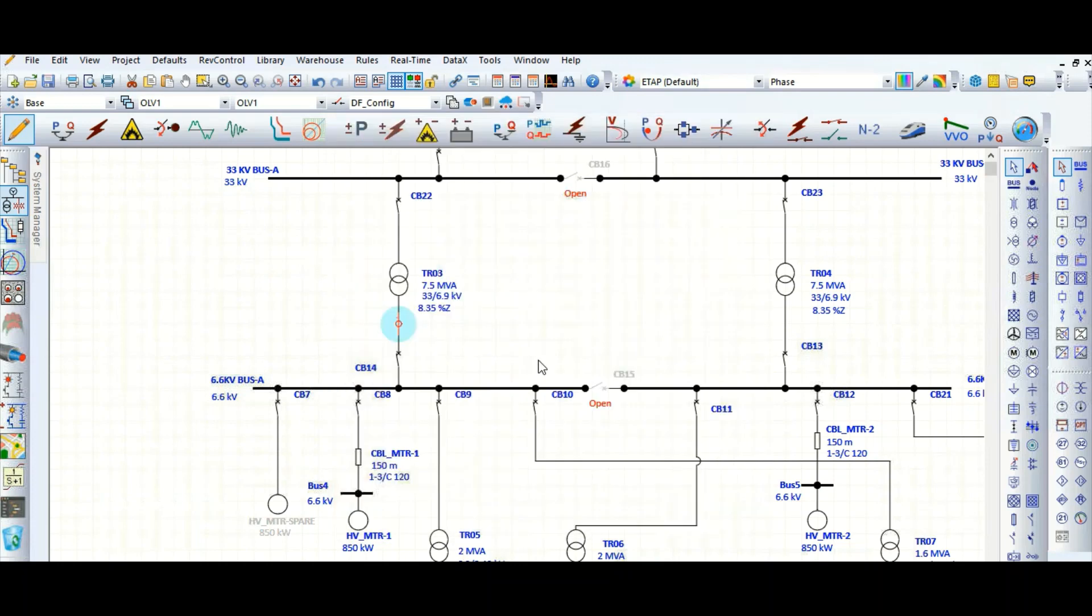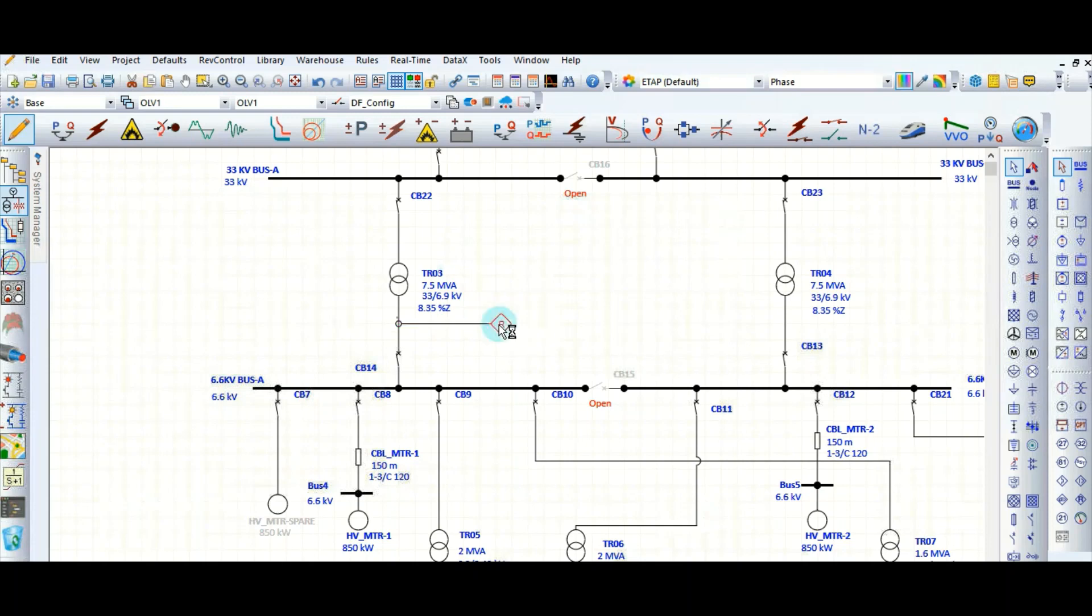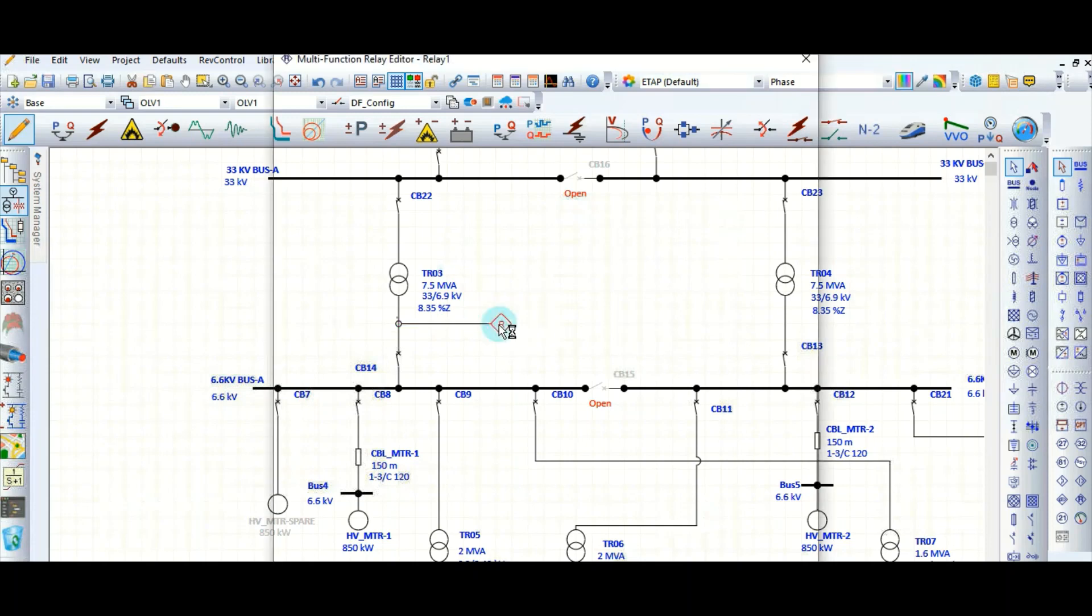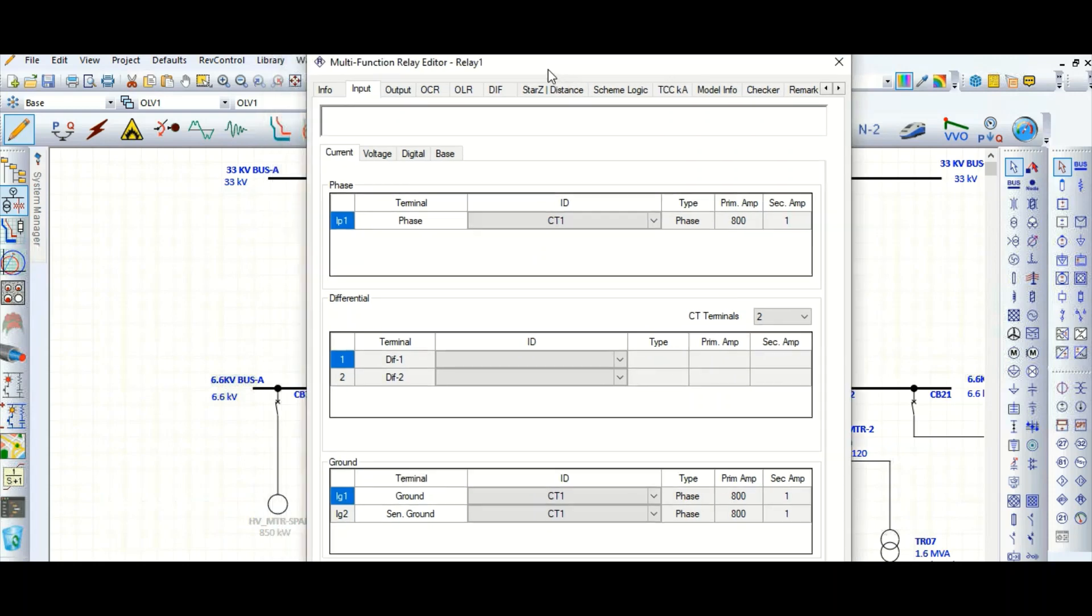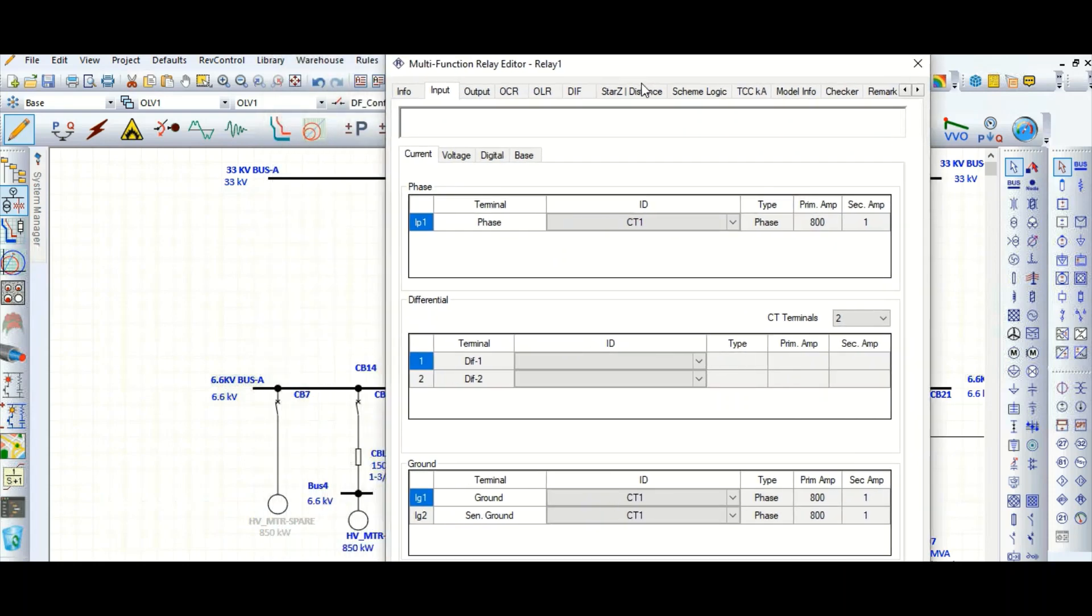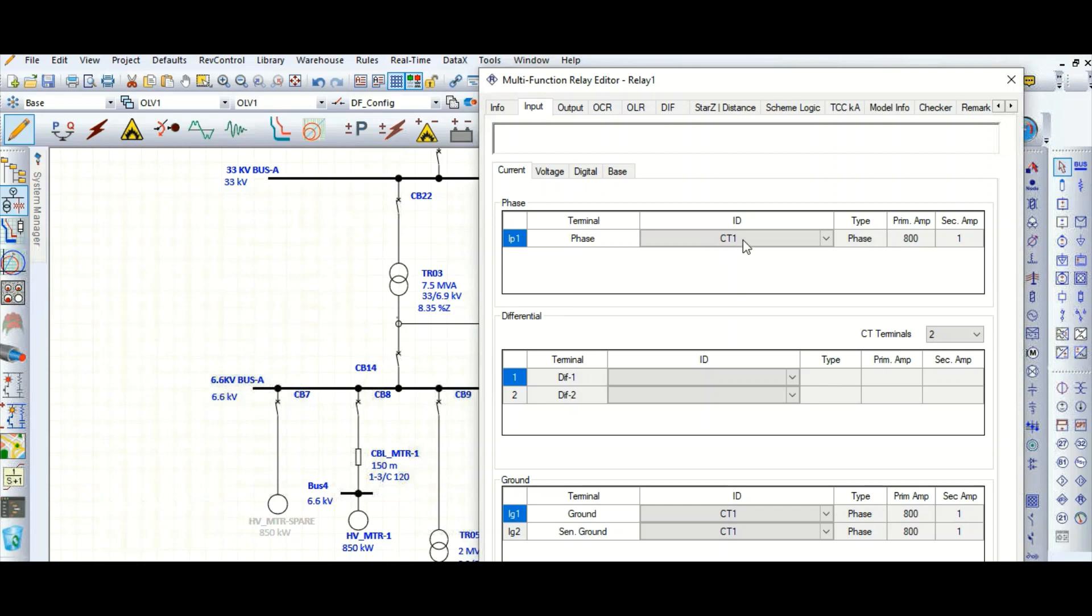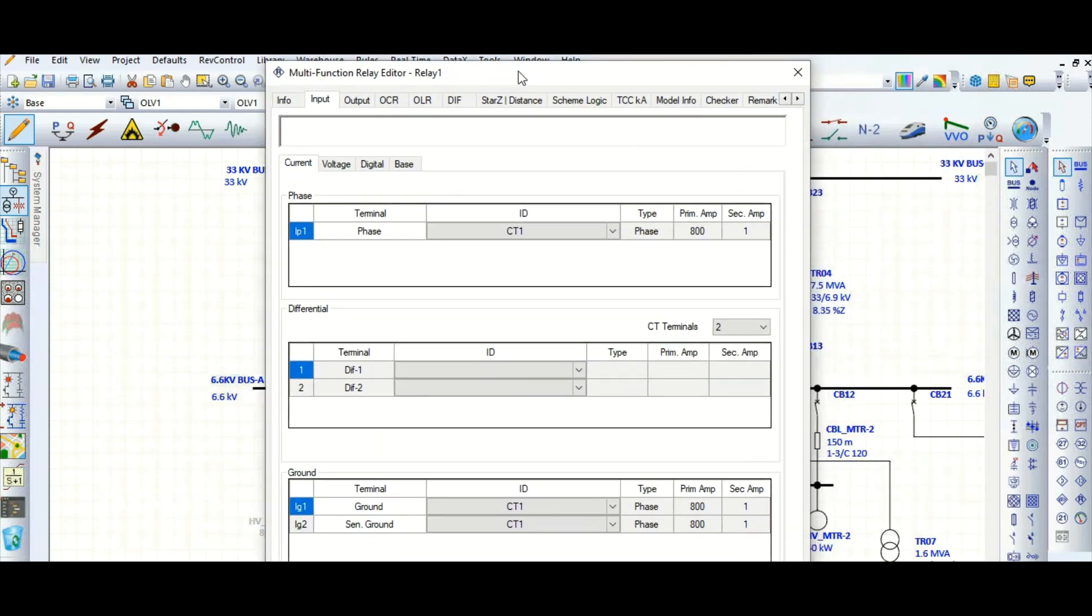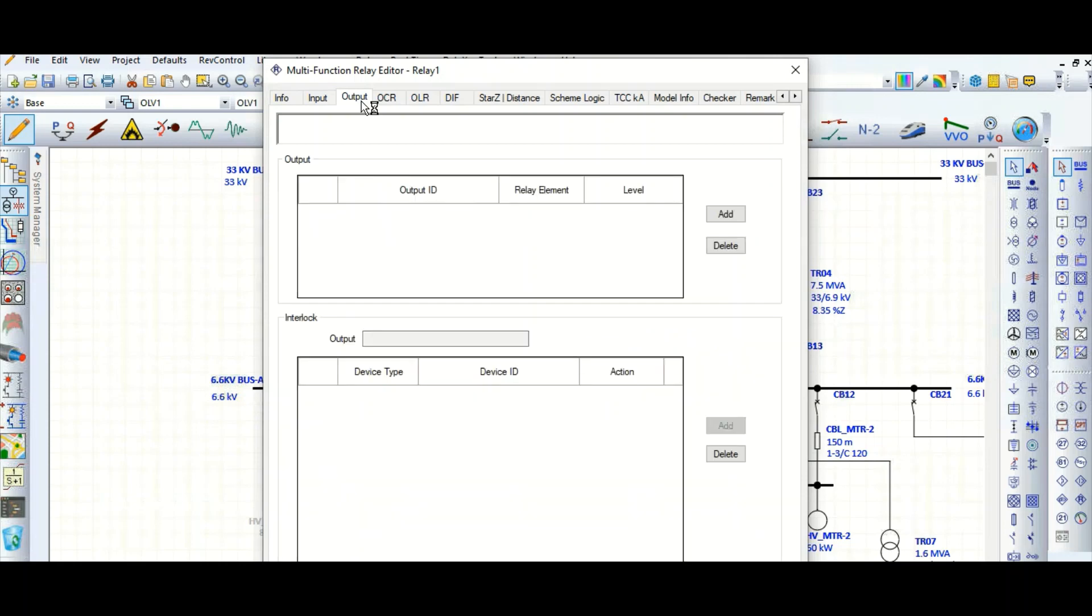Now let's select one relay here. This is the multifunction relay. Now going to the parameter here, so this input we need to define—this input, that means CT input. It has automatically taken this CT1 and 800 by 1 is the CT ratio. Okay, that's okay. Output.